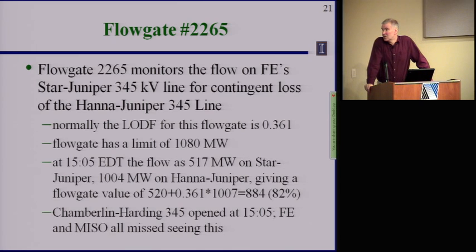The line outage distribution factor says if the Hanna-Juniper line were to trip, how much of that flow would go onto the Star-Juniper line. Normally the value is 0.361 - 36% of the flow would go onto that line.